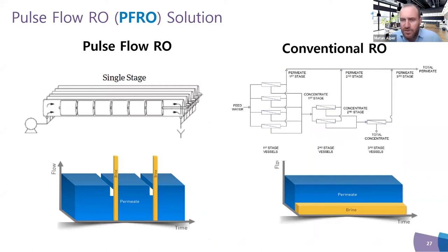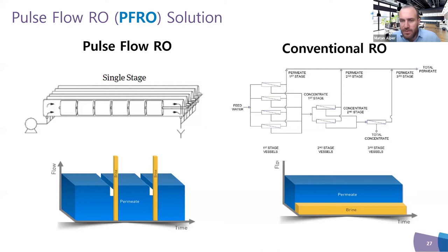The second high-recovery solution is the PFRO, Pulse Flow RO. A classic standard RO operates at constant conditions — typically a three-stage system in a one-to-two ratio from stage to stage — to maintain minimum brine flow and sufficient shear force in the last membranes. The PFRO takes a different approach with alternating flows, eliminating the need for this ratio. It operates at high recoveries in a single-stage configuration, creating sufficient shear force through its alternating flow regime.